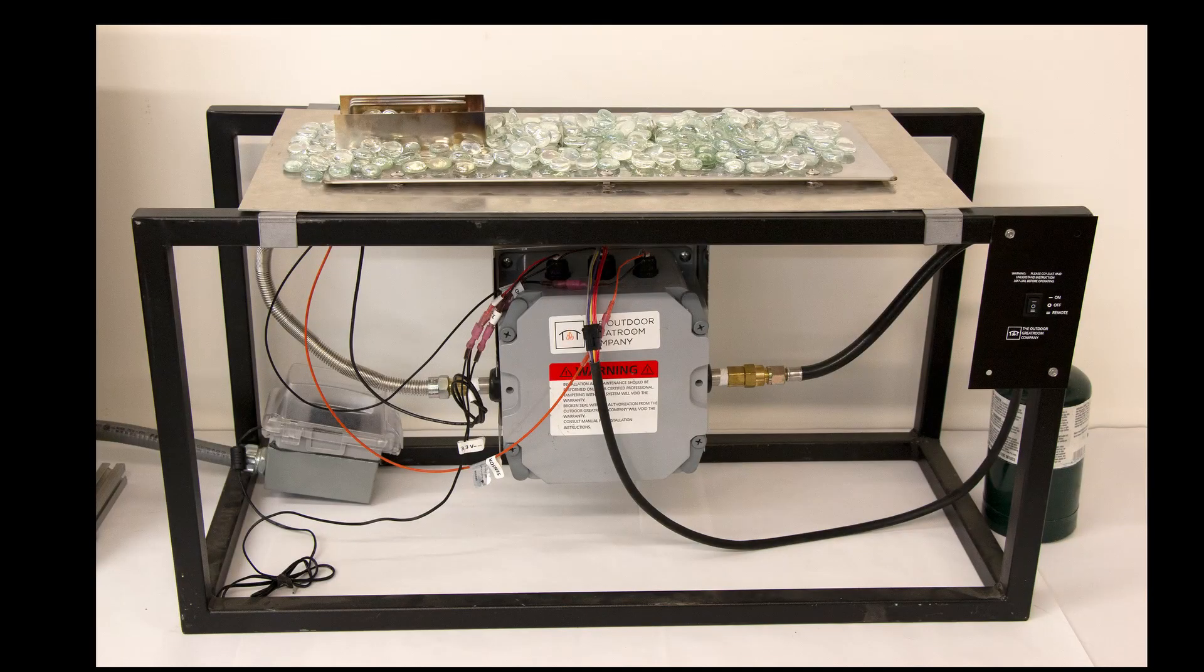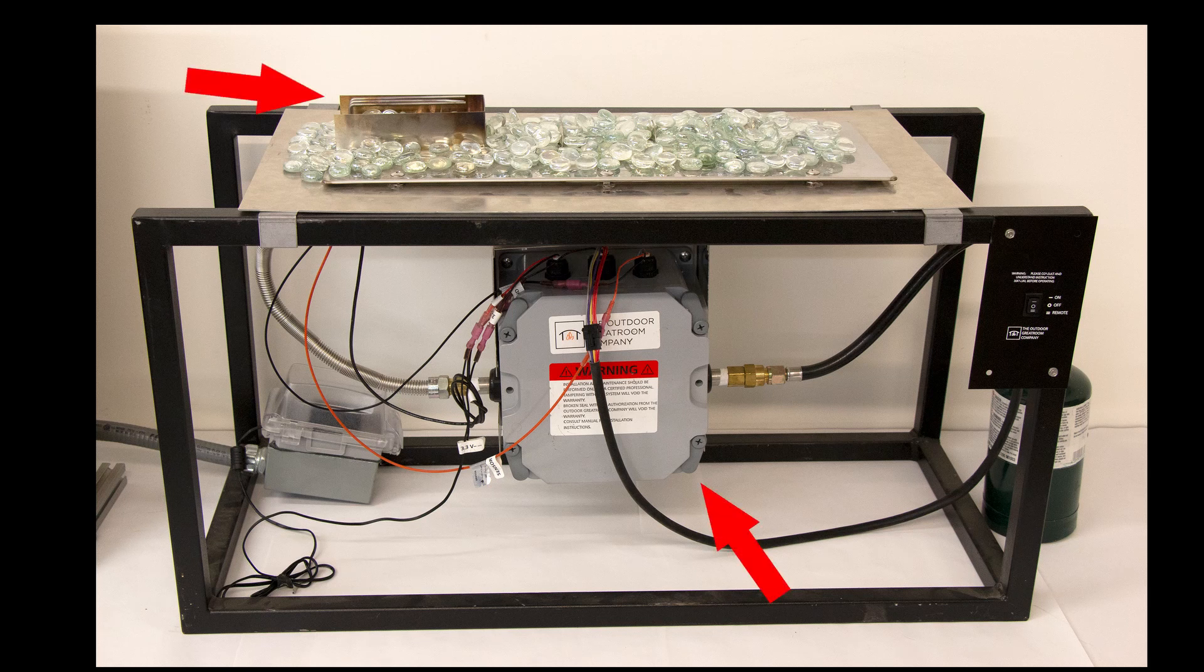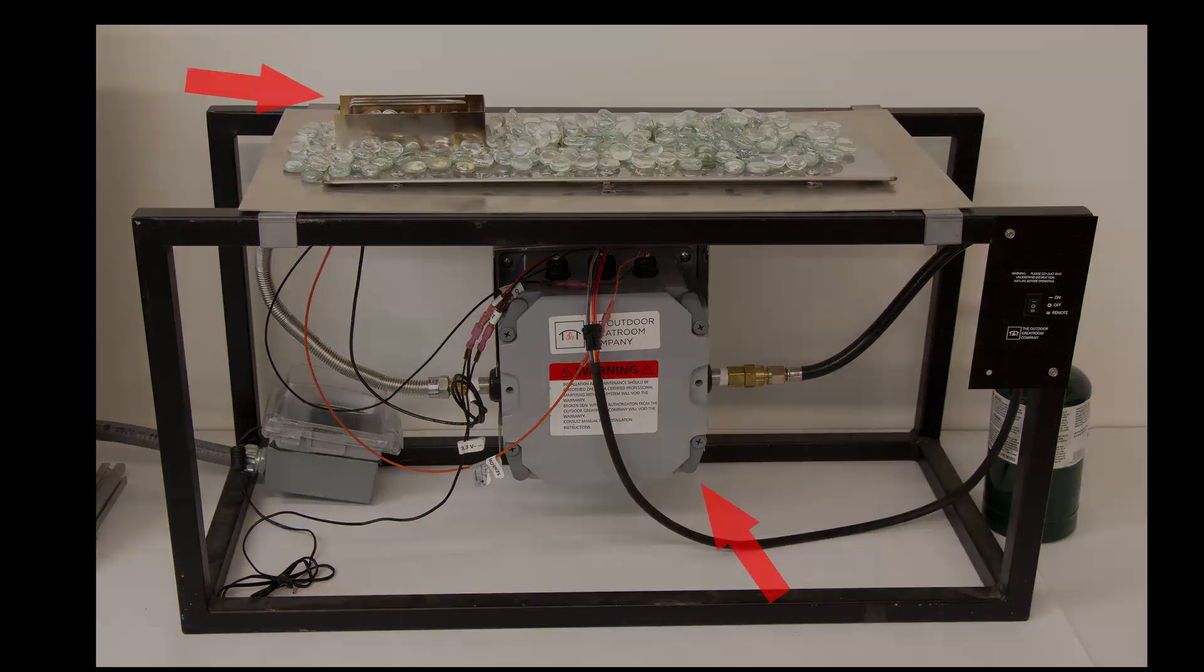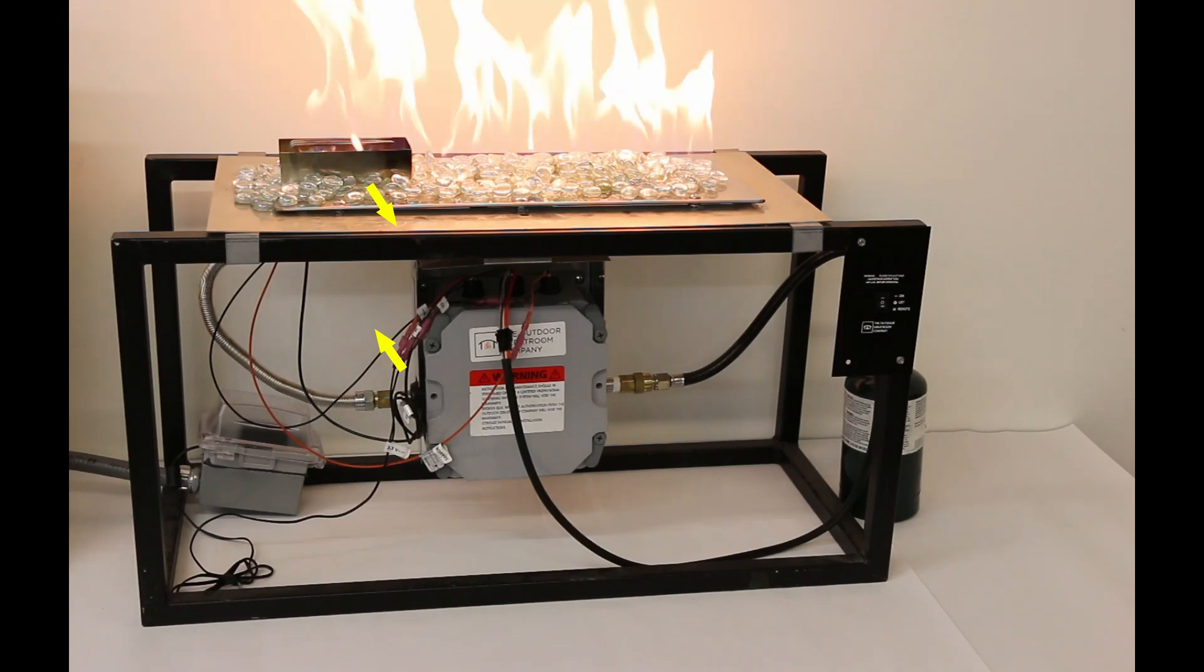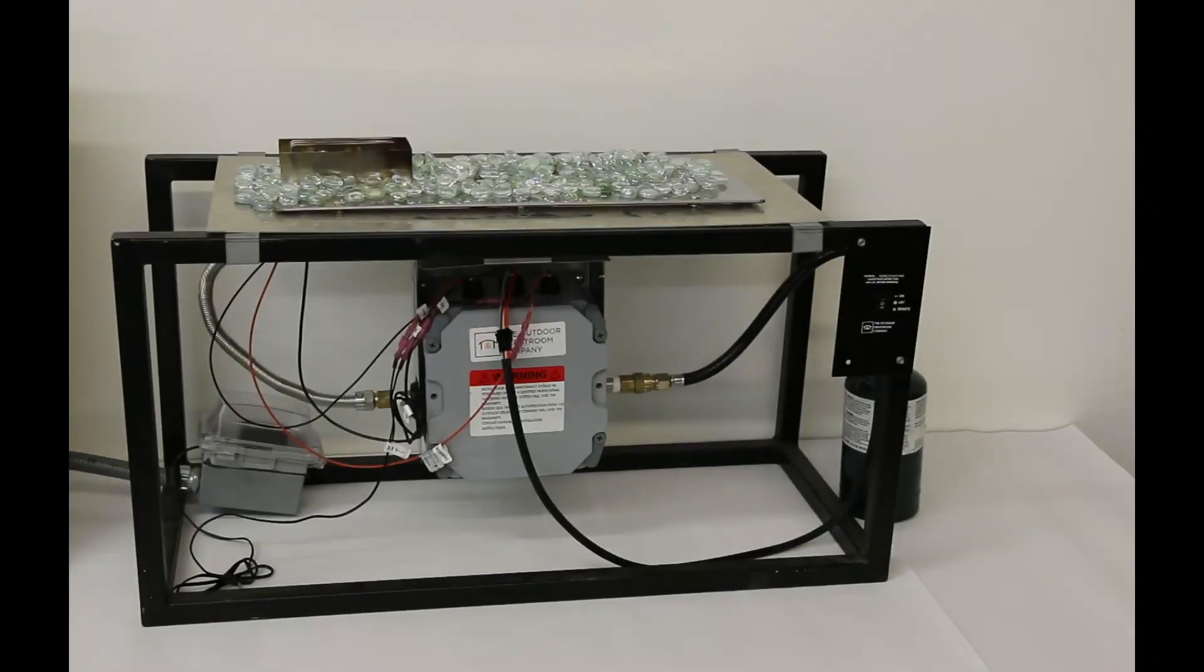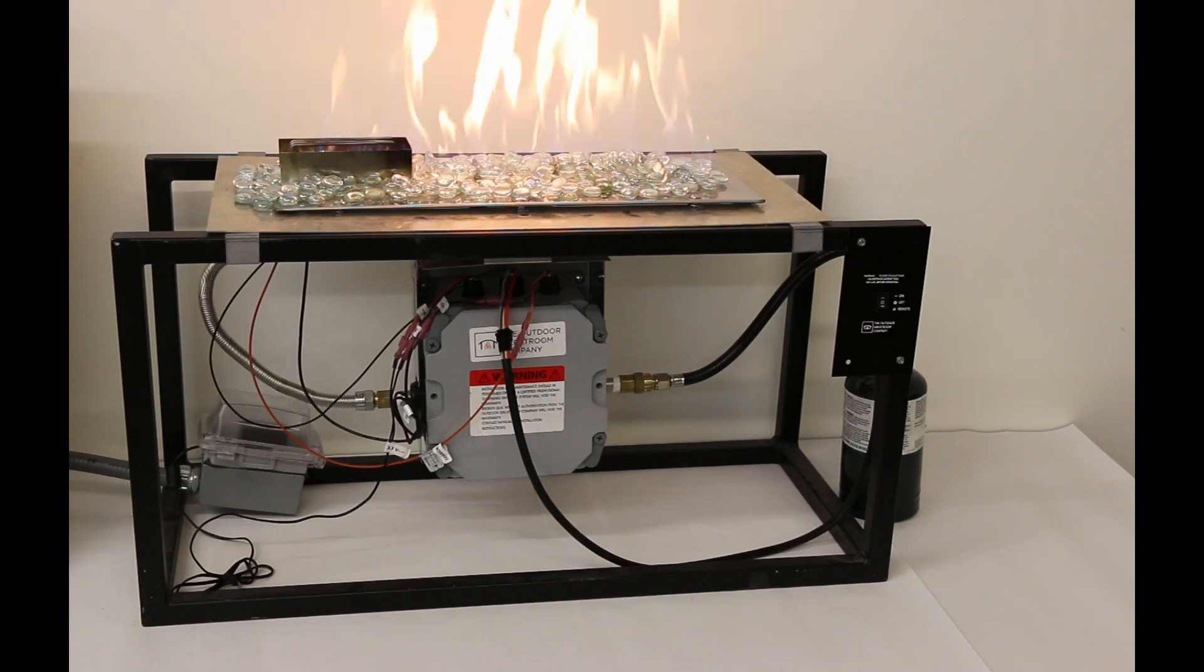Going one step deeper on this sequence, the module and electrode system are constantly interacting with each other. While in operation, the module is constantly receiving a signal to determine if a flame is present. If flame is present, the system will simply stay on. If the flame's signal is ever interrupted, the module will begin to spark again to reignite. When the system regains the flame signal, the sparking will stop. The system will shut down if a re-ignition attempt goes longer than 12 seconds.